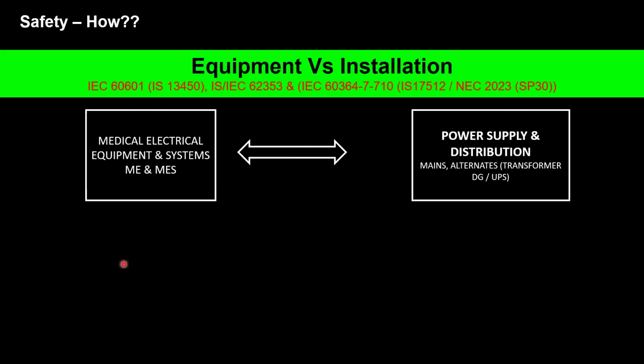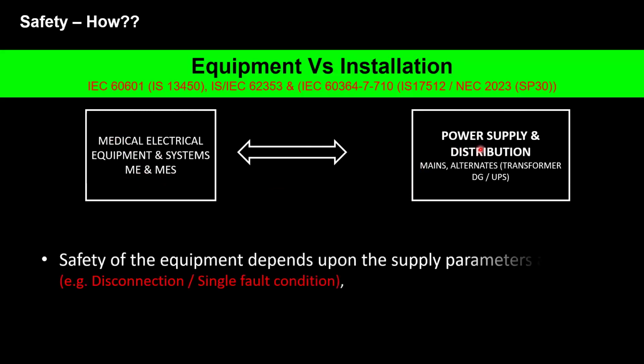In a nutshell, for example, equipment versus the installation. Medical electrical equipment and medical electrical system, they are classified. That means the electrical apparatus which is used in a medical location. Most often, the power supply and distribution decide the safety of medical equipment. For example, the safety of equipment depends upon the supply parameters as well. Sometimes disconnection, single fault condition.